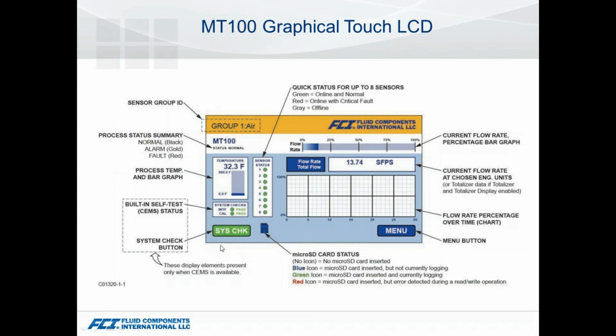With an option for CEMS, we have the ability to do a system check from the display. Without the CEMS option, you can do it through the interface. But CEMS is more geared towards the EPA requirement to do some sort of interference and drift check on your meter every 24 hours. So this device has that capability.